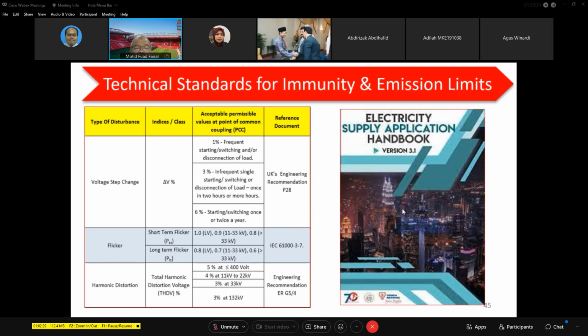The same goes for harmonics. The limit is given here, 3% at 132 kV. The voltage must not be distorted: 3% at 33 kV, 4% at 11 kV, 5% at the LV side. So this must not be introduced to the system.